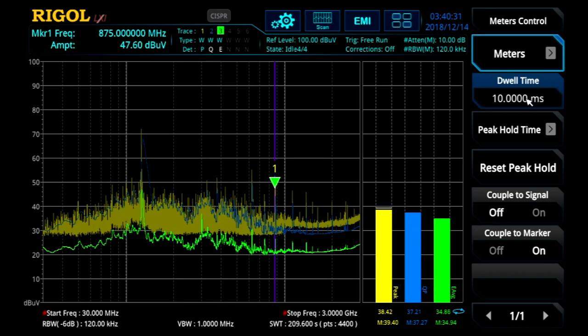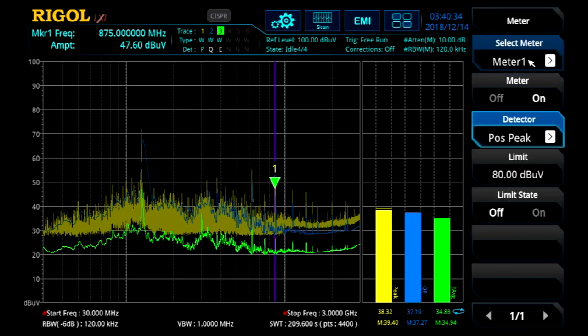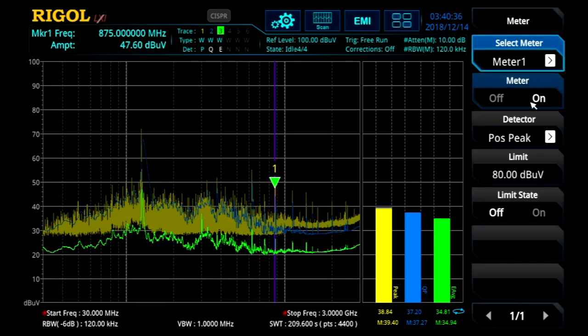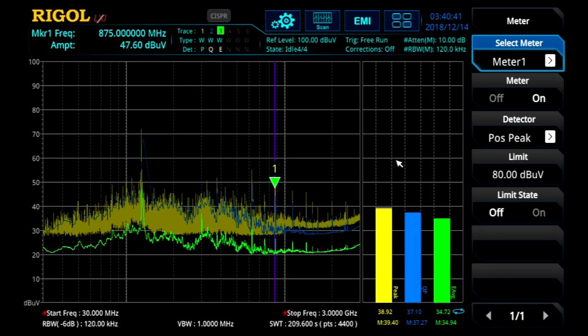Here we can set the dwell time for these measurements. We can also go in individually to each meter and set the detector value, and set an individual limit and limit point for each detector. Here you can see we're using the peak, quasi-peak, and EMI average detectors for these three meters.